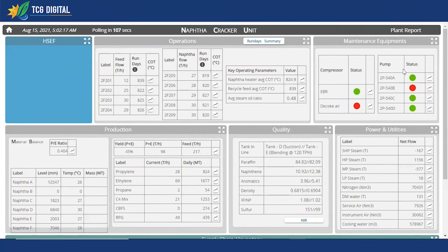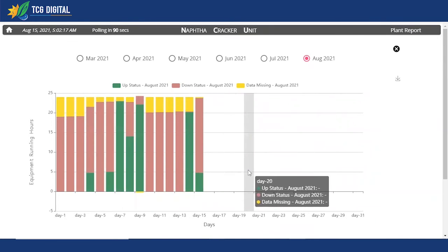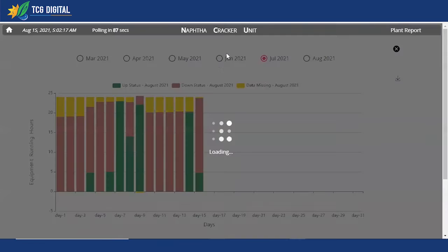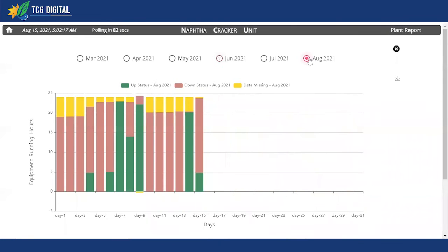For example, you can see which of the equipments are up and running. You can see decoke air is down — that's why it's in red. You can choose to do a drill-down here. When you drill down, you can see further details for decoke air: you can track performance across different months, look at the trend analysis, and also do different root cause analysis. These insights can help in preventive maintenance activities.